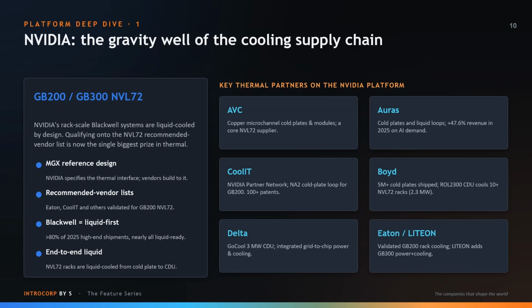Look at the partners: AVC, copper microchannel cold plates, a core NVL72 supplier. Auras, cold plates and loops, with revenue jumping nearly 48% in 2025 on this demand. CoolIT, an NVIDIA partner network member with its NA2 cold plate loop built for GB200, backed by over 100 patents. Boyd, which has shipped more than 5 million cold plates and whose ROL2300 CDU cools 10 plus NVL72 racks. And Delta, Eaton, and LITEON rounding out CDUs, rack cooling, and power. The message: winning NVIDIA is transformational for any thermal supplier.